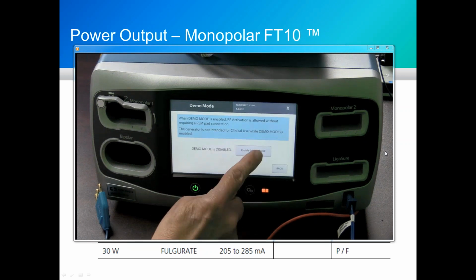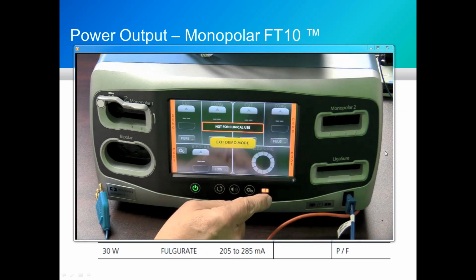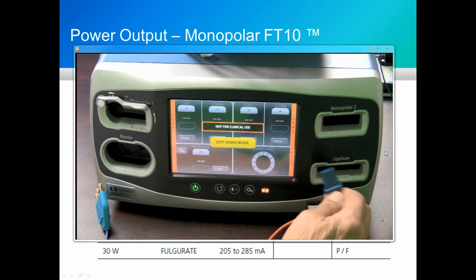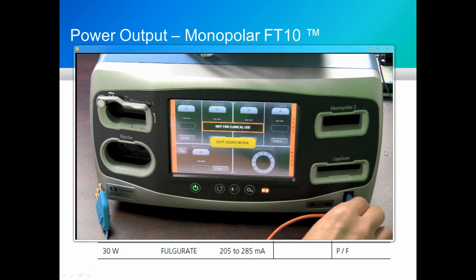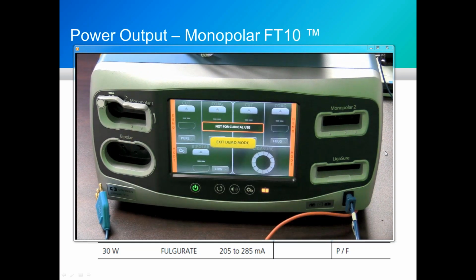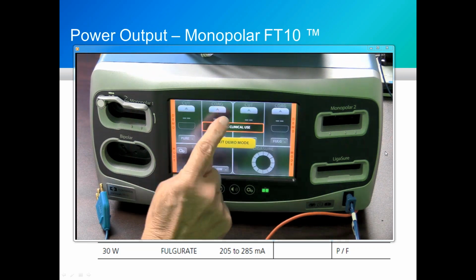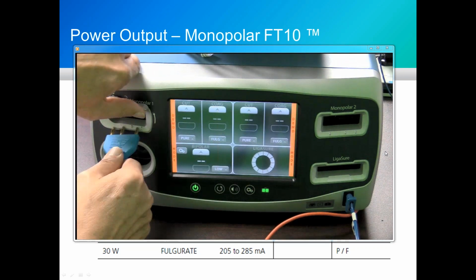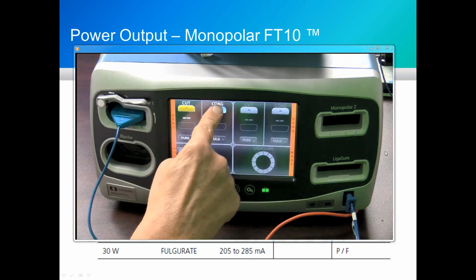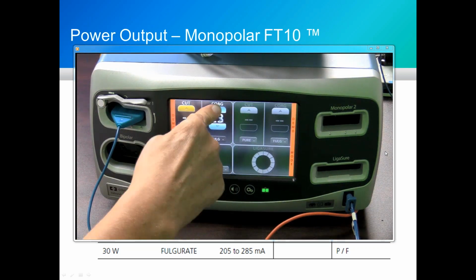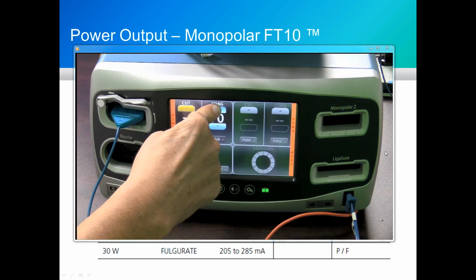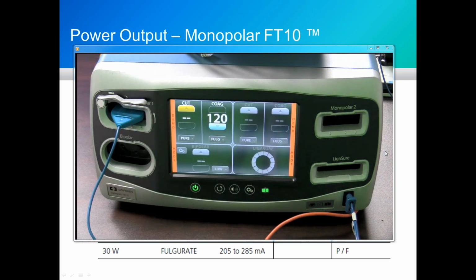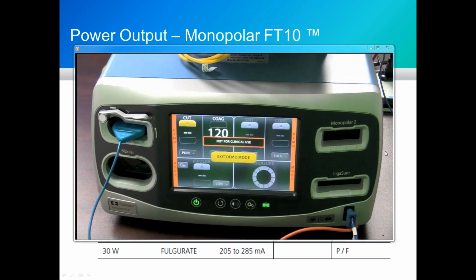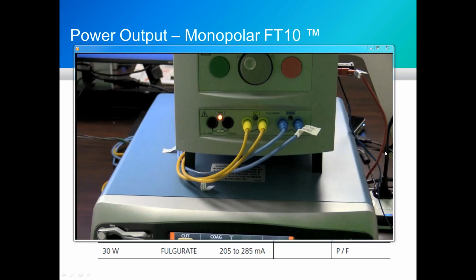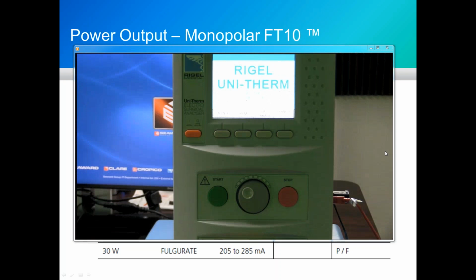I'm going into demo mode, enable demo mode. I'm using a REM connector that has that white pin removed, so it's a little different than what we use for our REM testing. Notice that my display is not active yet until I put my pencil in. You don't have to worry about holding the button down on this unit. That was a bit of a concern on the Triad, where you're supposed to press that and release it a little bit, but you can just hold that button, set it for your power. In this case, we're looking for 120 watts.